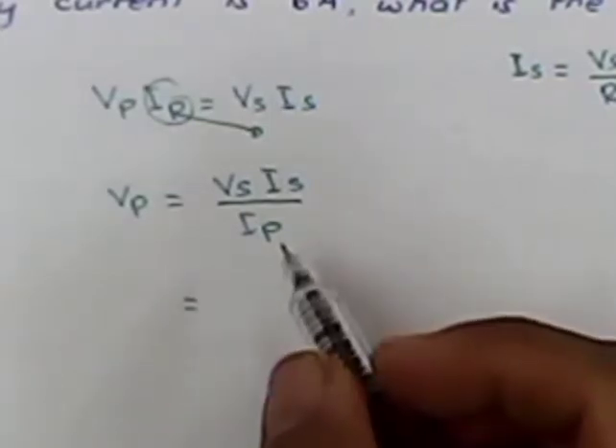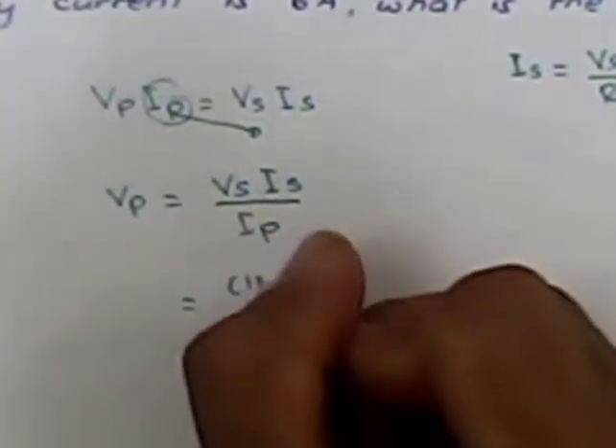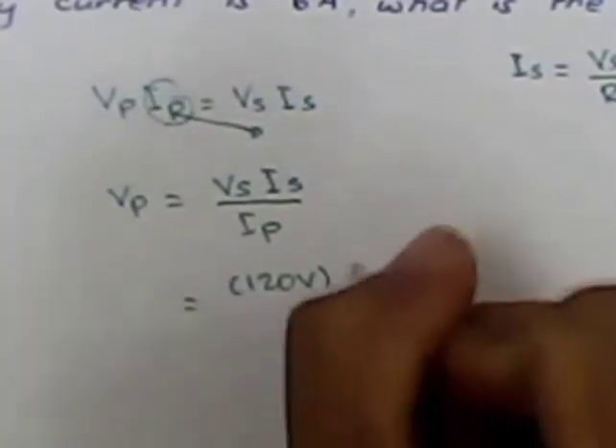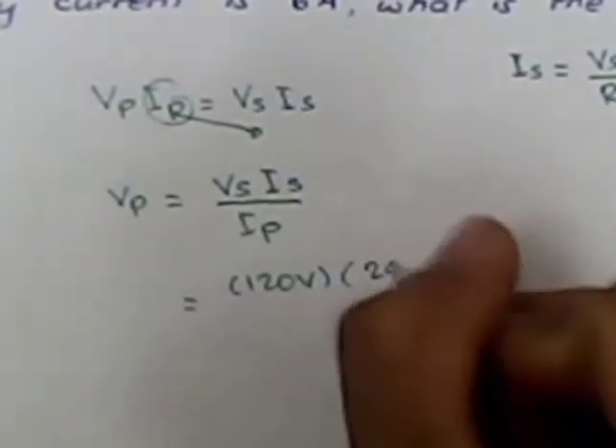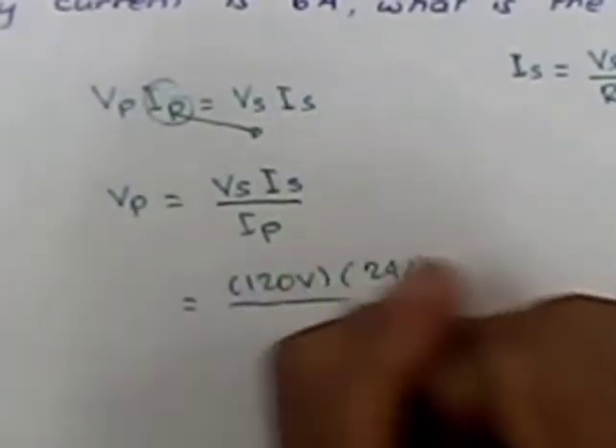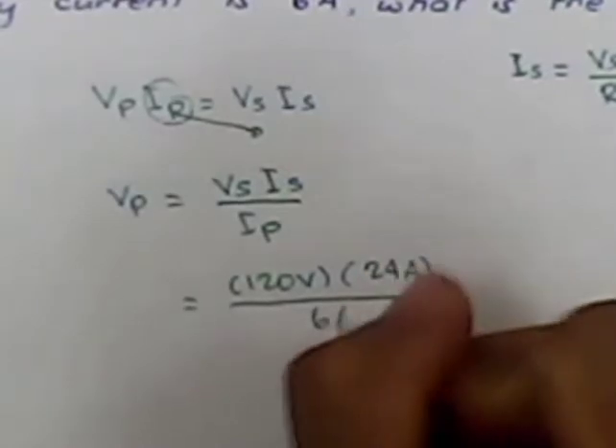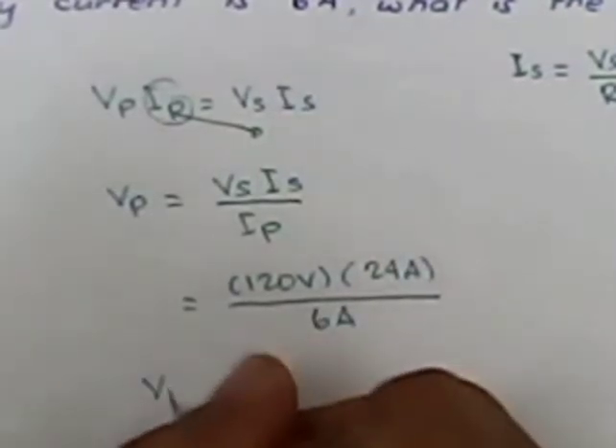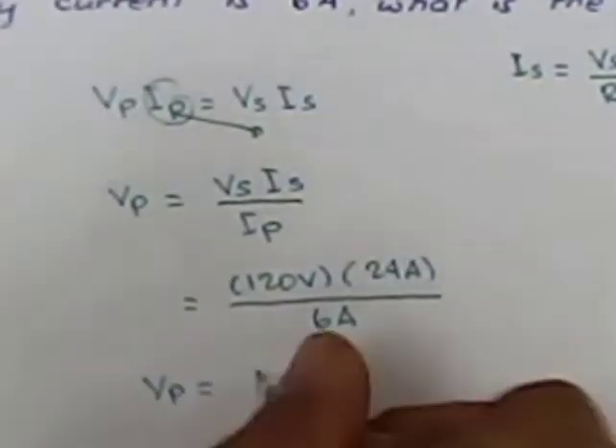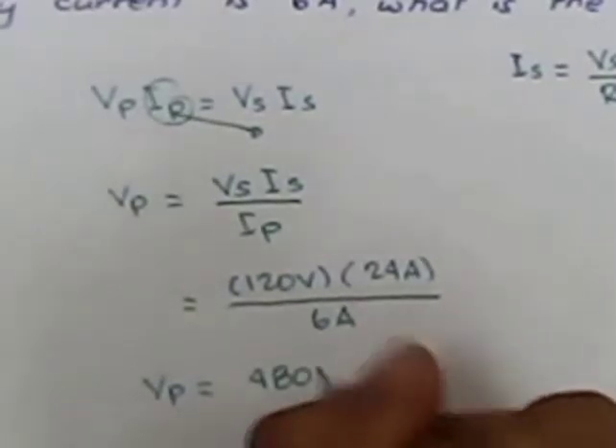Substituting the values, 120 volts multiply this by 24 amperes, divide this by 6 amperes. The voltage of the primary winding is 480 volts.